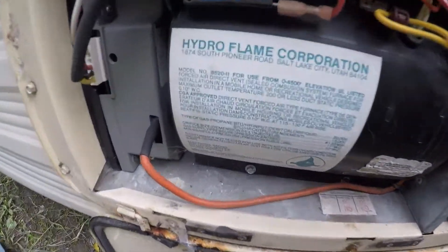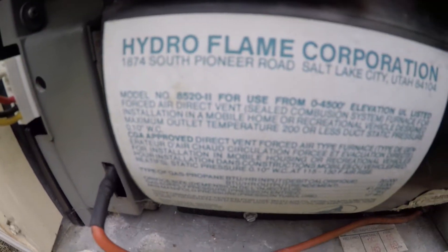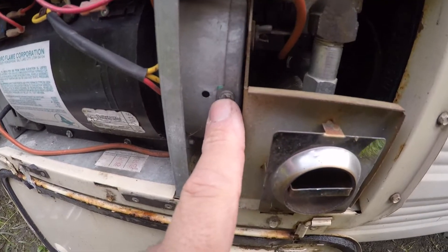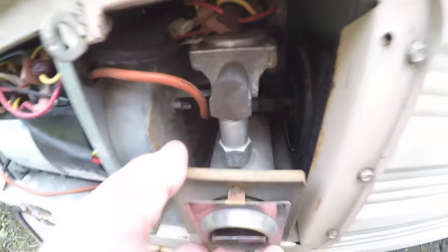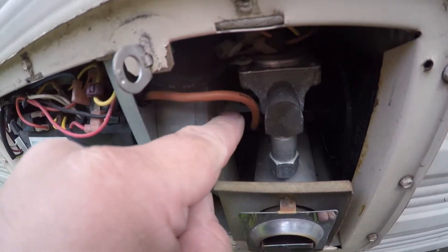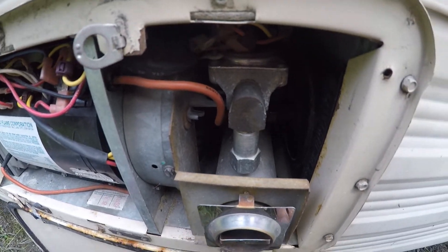So this one is a Hydro Flame model 8520-II. What we've got to take out: there's a screw there, a screw back there, a screw up there, and a screw down there. Then this whole assembly pulls out as one piece. We also have to take this wing nut off too, so we're going to go ahead and do that.